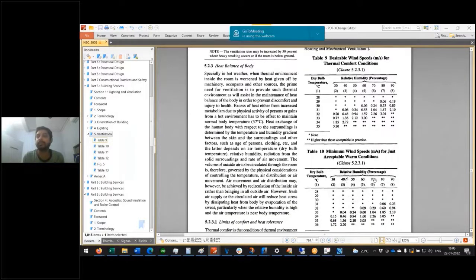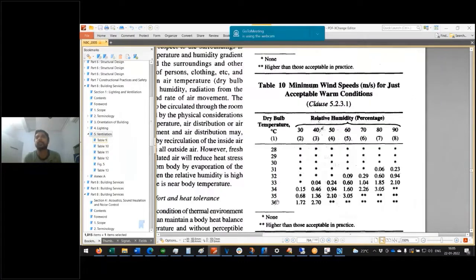Even just acceptable is fine, you can use these conditions. Because just acceptable goes up to 36 degrees Celsius, and at 40 we don't encounter 90% relative humidity. But even for the internal space, if it's a dining space and you have a high wall, obviously you can reduce the temperature itself to about 34 degrees, and then at 80%, if you ensure this 3.05 meters per second, this is really high, but if you can ensure this with air changes, you'll have to calculate.